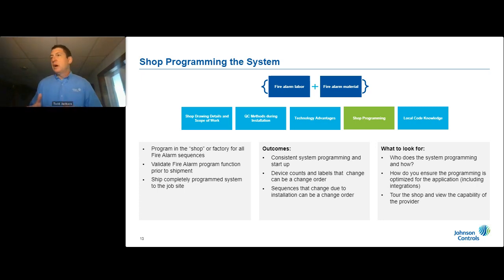So the outcomes this produces are consistent system programming and startup, and device counts and labels that, if they change—let's take a scenario. You've got a three-story building, call it a medical office building. The panel shows up, you put it on the wall, you terminate the circuits, and all of a sudden there are four more devices that need to be programmed. Well, something changed from the time that system was programmed to what got installed.